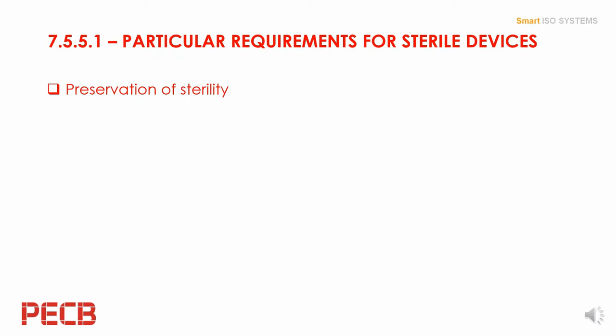Particular requirements for sterile medical devices. This is again a new requirement that elaborates on particular requirements for sterile medical devices. If you manufacture sterile product, you have to take additional measures to make sure that the sterility will be preserved. Whatever you plan to ship and however long it takes you to get there, some questions to ask are: how do you demonstrate that the product is going to remain sterile? Again, you need to have the validation records to prove that your product meets this requirement.